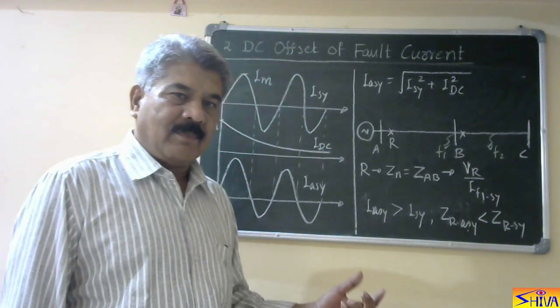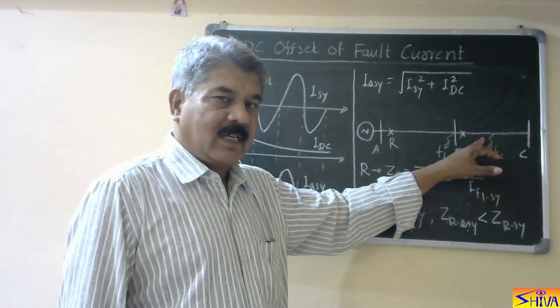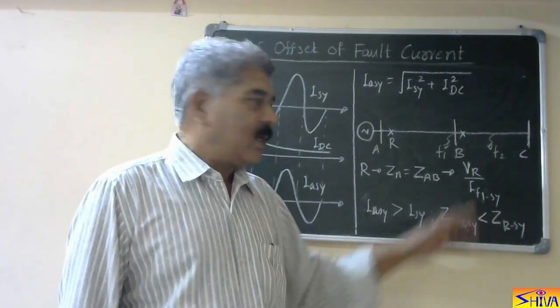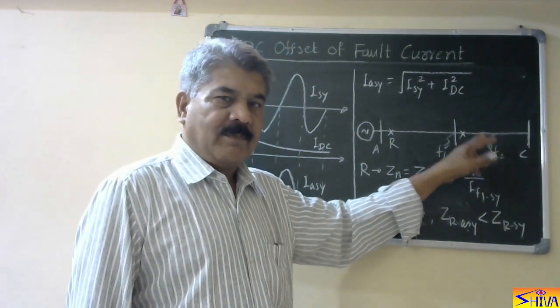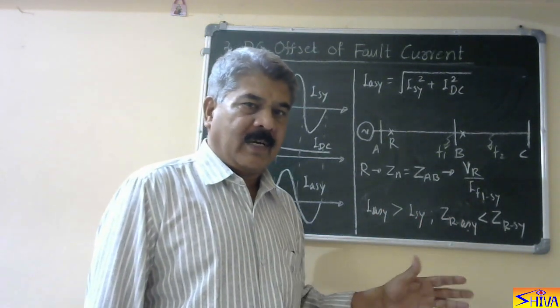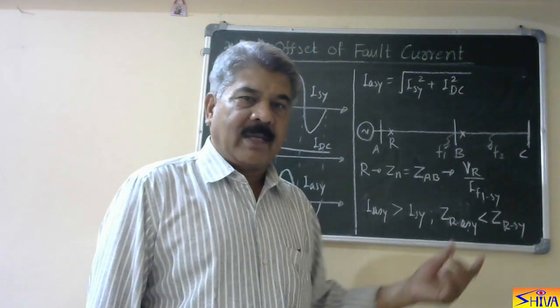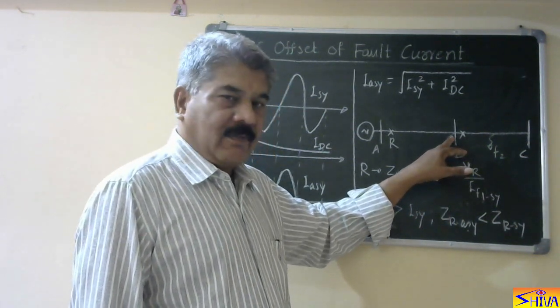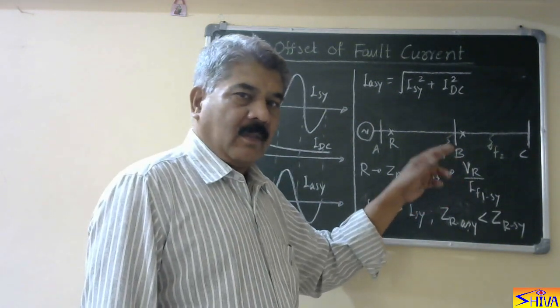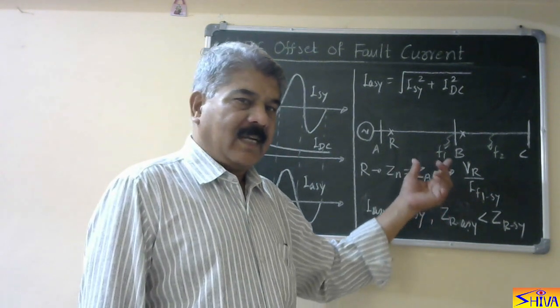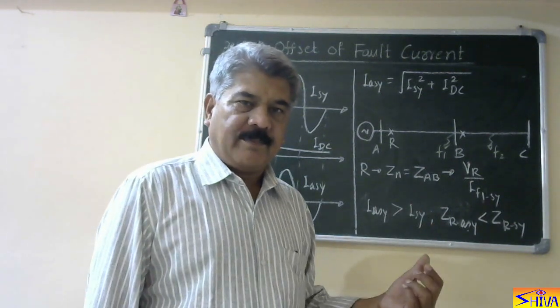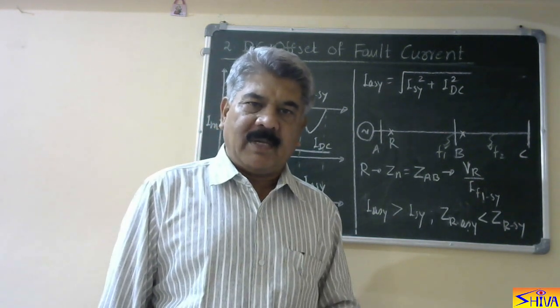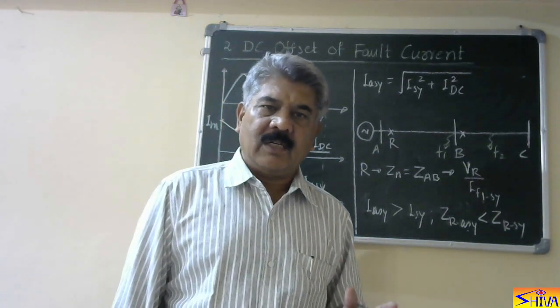So as the impedance measured is less, the relay is going to overreach. For example, if a fault occurs at point F2 — that is in the next section — and it has a symmetrical fault current component of smaller magnitude, then considering only the symmetrical component, the impedance measured will be more than ZN and the relay will not operate. But if DC offset is present, the overall magnitude of the asymmetrical fault current at F2 can equal the magnitude of the fault current at F1 with symmetrical component only. So the impedance measured by the relay becomes less than the impedance setting and the relay operates. Due to DC offset of the fault current, all distance relays — whether mho relay, impedance relay, or reactance relay — overreach.